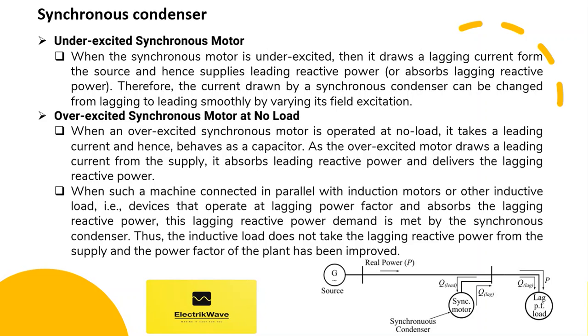When an overexcited synchronous motor is operated at no load, it takes a leading current and hence behaves as a capacitor. As the overexcited motor draws a leading current from the supply, it absorbs leading reactive power and delivers lagging reactive power. When such a machine is connected in parallel with induction motors or other inductive loads — devices that operate at lagging power factor and absorb lagging reactive power — this lagging reactive power demand is met by the synchronous condenser. Thus, the inductive load does not take the lagging reactive power from the supply and the power factor of the plant has been improved.